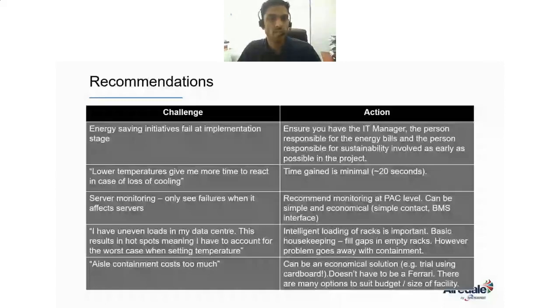Server monitoring only sees failures when it affects the server. So what we say is that we need to recommend monitoring at the PAC level, which can be done in a very simple and economical way by simply connecting with a hardware contact or a BMS interface contact. Like we say, prevention is better than cure. So we have to monitor from the PAC level before it affects the servers.